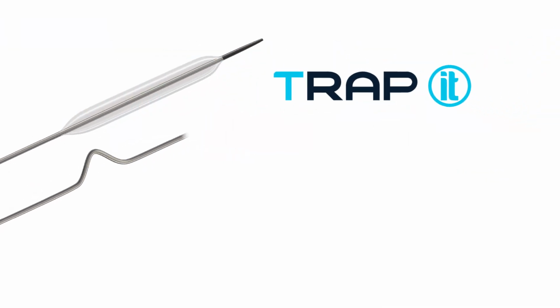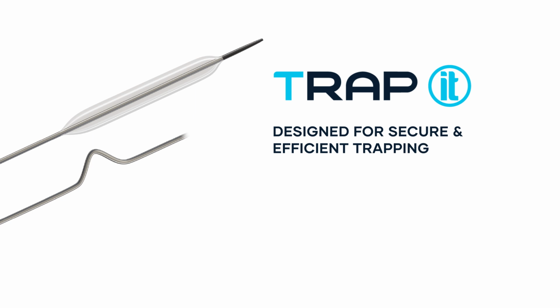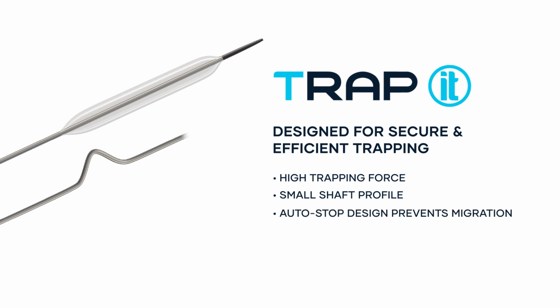So to summarize, the TrapIT balloon is designed for secure and efficient trapping. It does not have a hydrophilic coating, so it provides high trapping force. It has a very small profile, so it allows more room in the guide for additional equipment. It has an auto-stop design on the shaft to prevent migration, and no X-rays are needed, with the exception, for example, when we're using a 100 centimeter TrapIT inside a 90 centimeter guide, then one should use fluoroscopy, or you should just use the marker for 90 centimeters on the TrapIT.